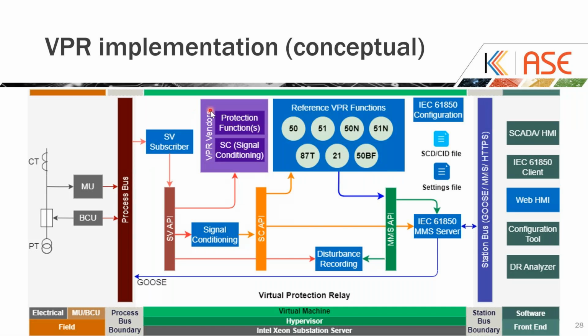So this is the VPR conceptual implementation, which we also developed as the reference for the evaluations and performance benchmarking of the VPAC platform. This is the overall architecture, with the VPR infrastructure, or VPR framework, as the backbone, implementing the IEC 61850 substation-based protection relay. It has all the essential IEC 61850 modules like the sample value subscriber, the GOOSE publish-subscribe modules, a reference disturbance recording module, as well as an MMS server implementation.